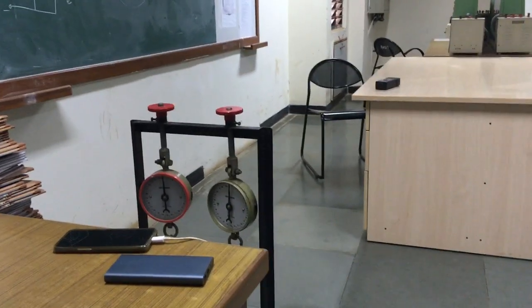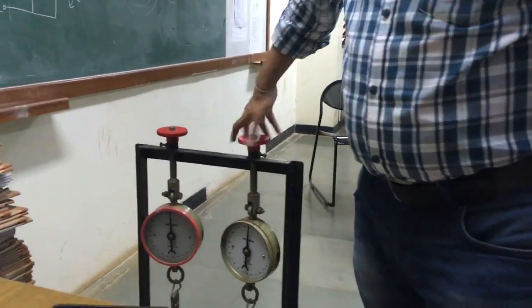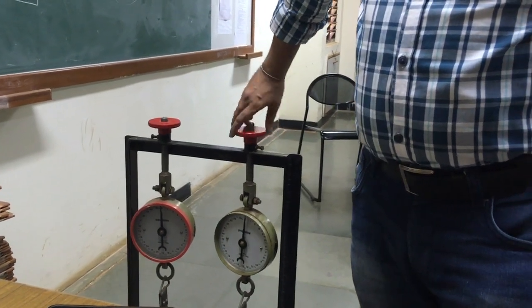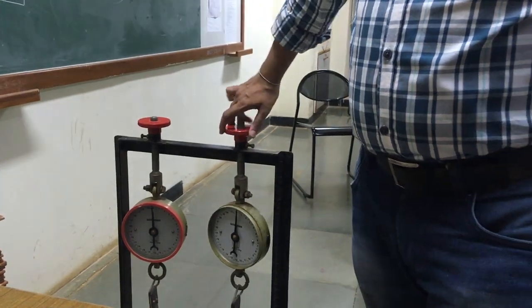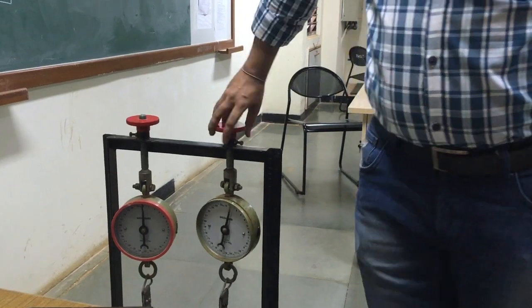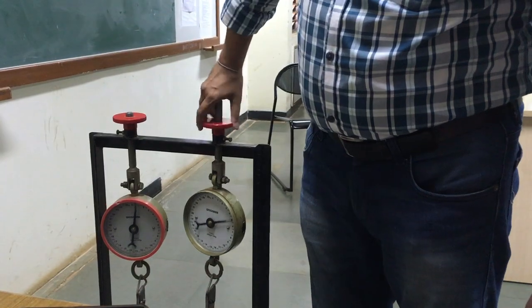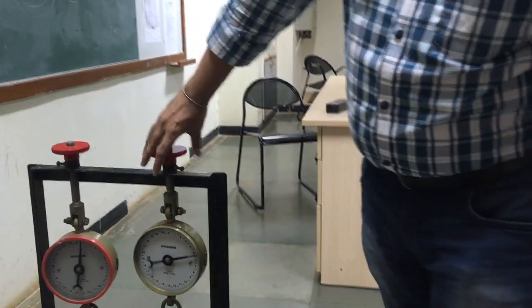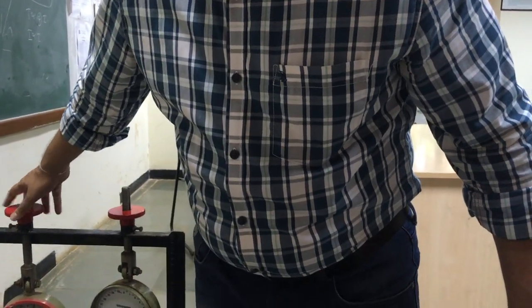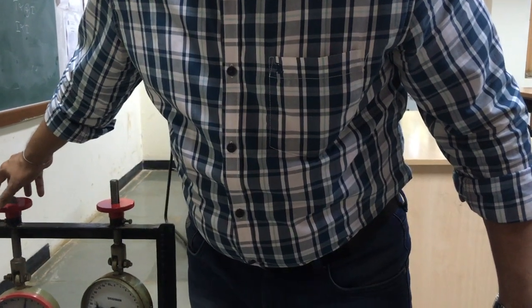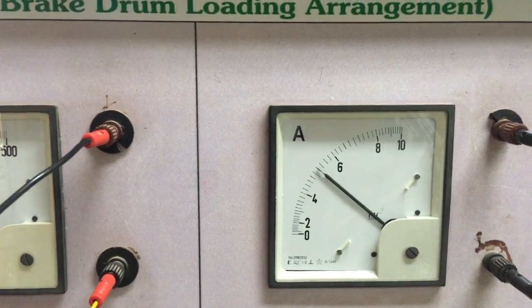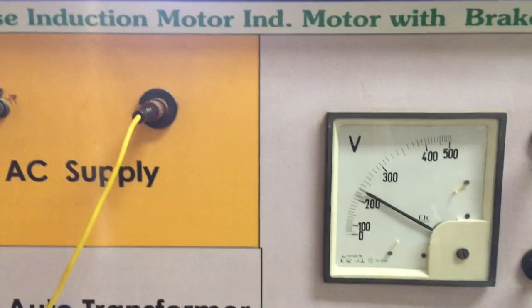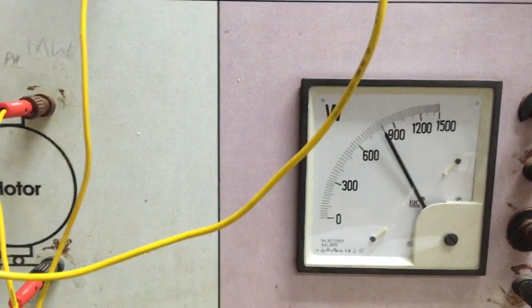Now we will gradually increase the load in steps of some current values, and we will see the readings. The no load current was 4.4 amperes. I will increase it to around 4.8 amps. Sorry, the no load current is 4.8 amps, not 4.4. I will increase the load up to around 5.2 amps. So line current is 5.2. Input voltage will almost remain constant at 230 volts. Power is 800 watts.